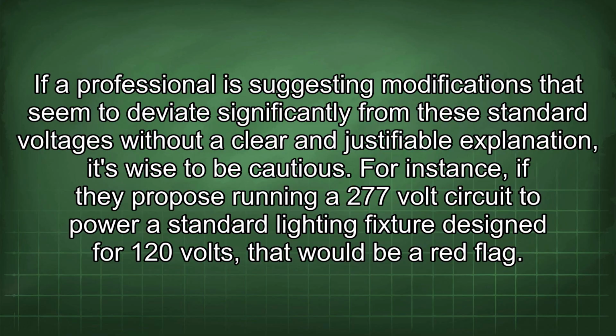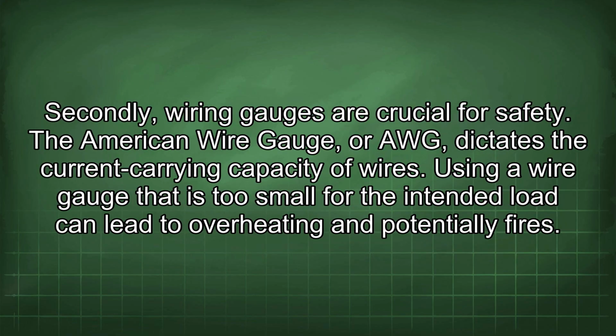For instance, if they propose running a 277-volt circuit to power a standard lighting fixture designed for 120 volts, that would be a red flag. Secondly, wiring gauges are crucial for safety. The American wire gauge, or AWG, dictates the current carrying capacity of wires. Using a wire gauge that is too small for the intended load can lead to overheating and potentially fires.